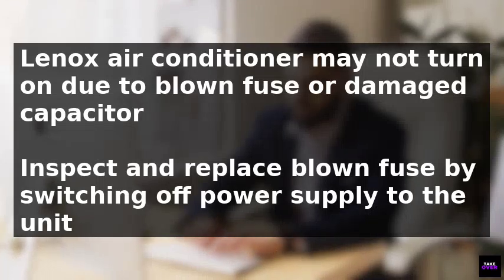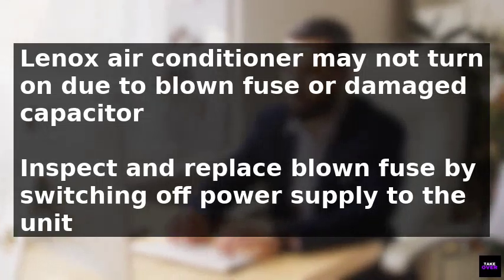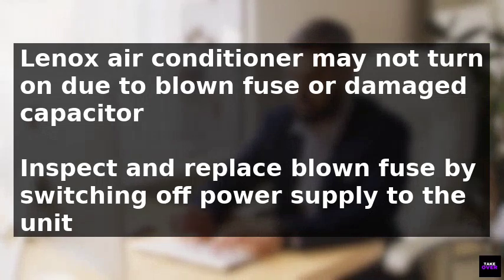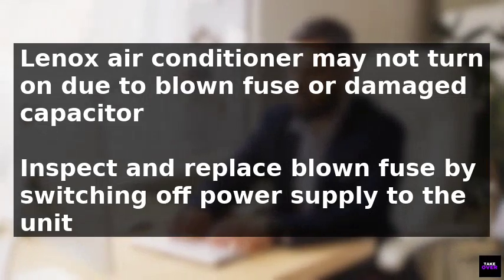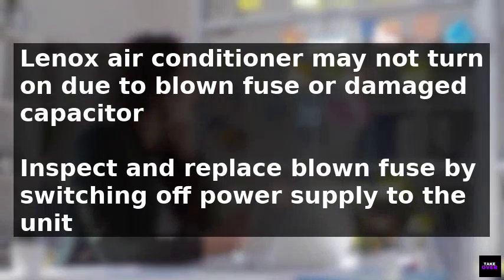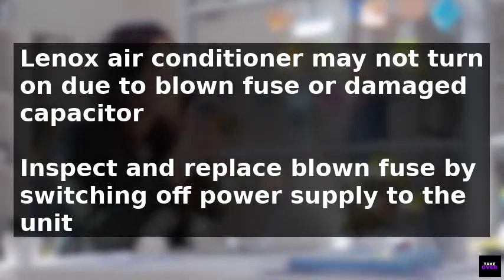A Lennox central air conditioner may not turn on due to a blown fuse or a damaged capacitor. To troubleshoot this issue, first inspect and replace the blown fuse by switching off the power supply to the unit and locating the fuse box, which is usually near the control panel or air handler unit.